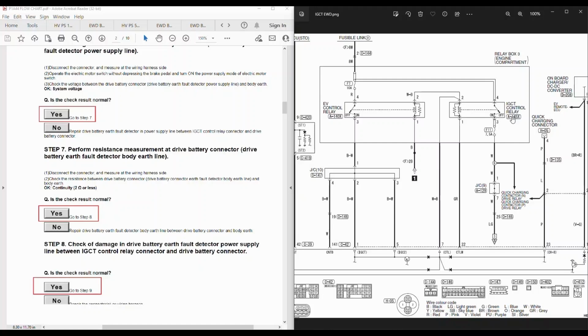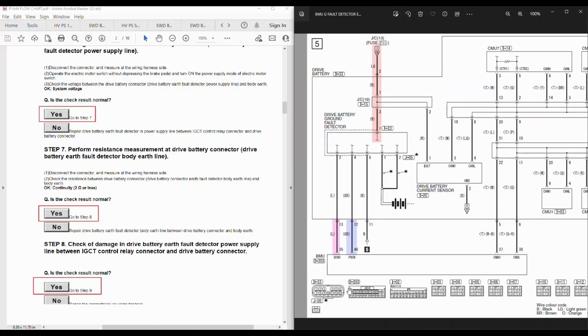Yeah, so here is our ignition control relay. So when that energizes via fuse 11, that then feeds various circuits off to the quick charge contactor relay, but also to other circuits inside the battery, one of which is our leak detector. So that is back to this one here. I didn't quite fully understand what that was saying, unless we're going to intrude inside the battery. So let's just go through that again.